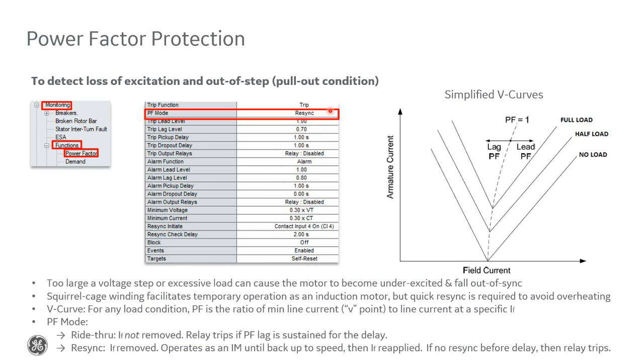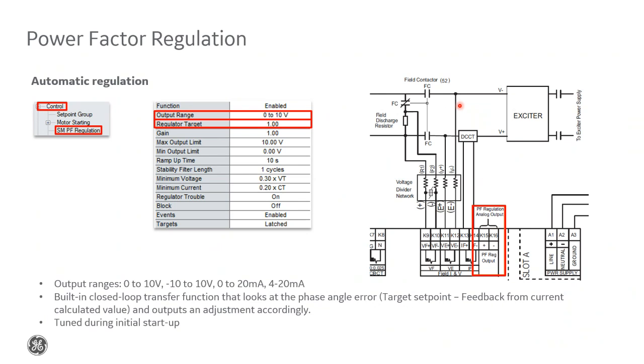So which option you choose here would probably depend how expensive the motor is, if it's driving a critical load, and if fluctuations in your power factor are frequent or considered normal in your application. Resync is definitely a safer option, but it does have a greater likelihood of affecting your process. Last quick note here on features. We do still have the automatic power factor regulation function that the SPM had on the 869.